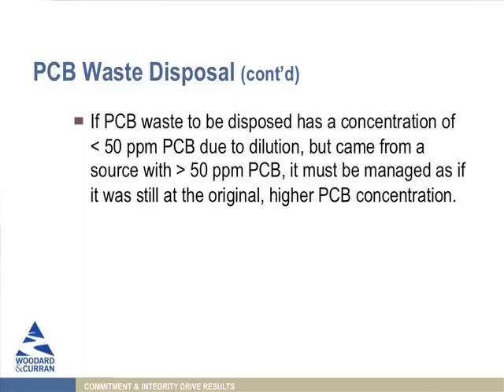One other key thing: if your PCB waste has a concentration less than 50 parts per million in the end, but it came from a source greater than 50 parts per million, it's got to be managed as if it was at that higher concentration. You cannot take advantage of the fact that it may have been diluted, whether deliberately or inadvertently. You have to treat it by what the original source was in the equipment, if something was leaking out, for example.